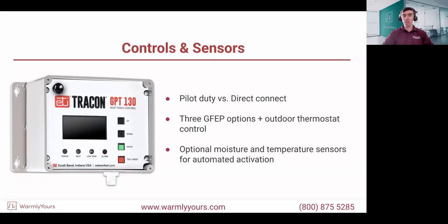But yes, most of these industrial and light commercial controls will have a built-in GFEP, depending on the type of system and type of application, I should say. You can have a more or less simple freeze protection system, where the goal of the control is to sense the temperature and make sure it never drops below that melting point. Typically, it would be predetermined, 38, 40 degrees or so.